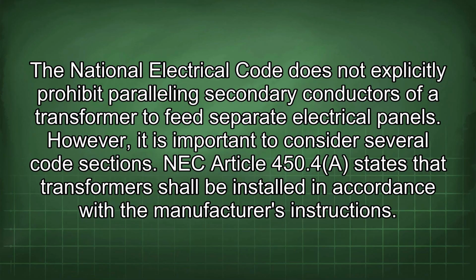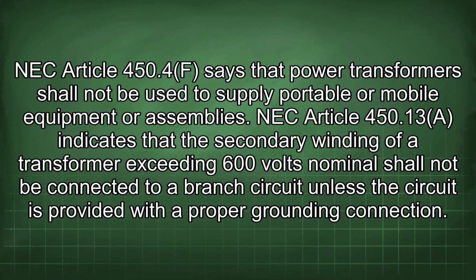The National Electrical Code does not explicitly prohibit paralleling secondary conductors of a transformer to feed separate electrical panels. However, it is important to consider several code sections. NEC Article 450.4 states that transformers shall be installed in accordance with the manufacturer's instructions. NEC Article 450.4f says that power transformers shall not be used to supply portable or mobile equipment or assemblies. NEC Article 450.13 indicates that the secondary winding of a transformer exceeding 600 volts nominal shall not be connected to a branch circuit unless the circuit is provided with a proper grounding connection.